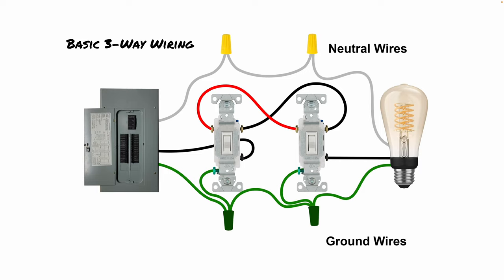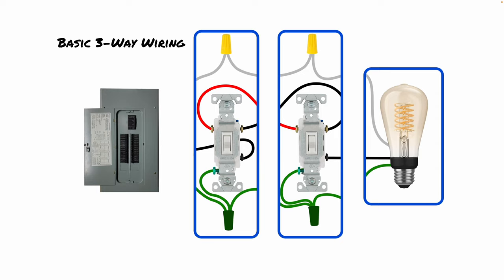Keep in mind that the wiring between the switches is 14-3, and the wiring from the electrical panel into the first switch box is 14-2, the standard wire. Off the last switch to the light fixture is also 14-2. So 14-3 is only used between the switches themselves. I've isolated each of the boxes so you can see the connections clearly, including the splices. Also, if the light fixture is wired into a metal box, make sure to connect the ground to the box itself.